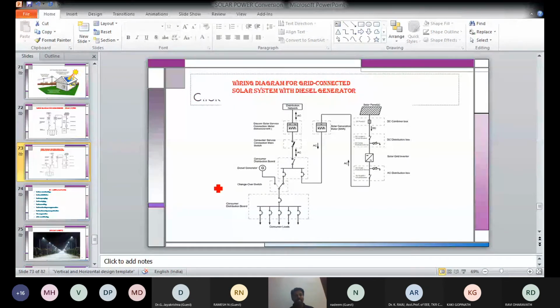This has to get synchronized with the diesel generator, because it will get synchronized with your grid now. Since diesel generator is connected, this inverter has to get synchronized with the diesel generator, and if excess power is there, it will go to the diesel generator now. So we need to be much more careful when going for such kind of things.